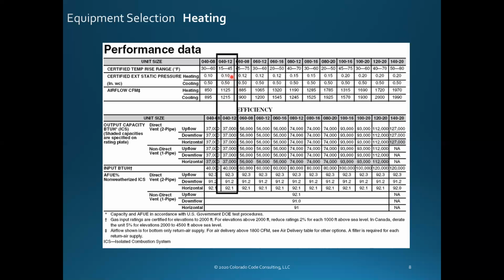So here it is. At 0.1, it was moving 1125 CFM, and at 0.5, it was moving 1215. Okay? That's what it was doing. That's it. Then we get down to the different capacities, and of course, you can set these furnaces 3 different ways as to what it's doing. It's got slightly different efficiencies depending on what you've done. And here is the ticket.